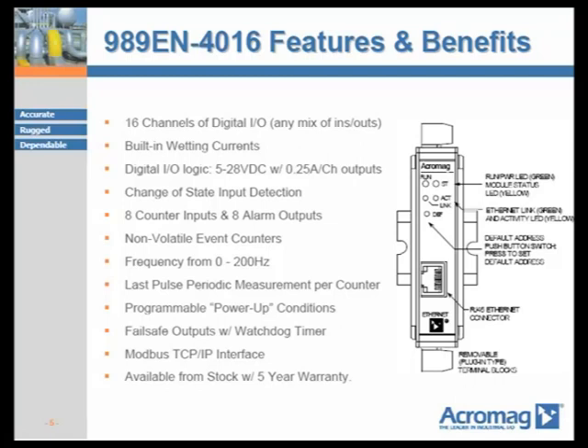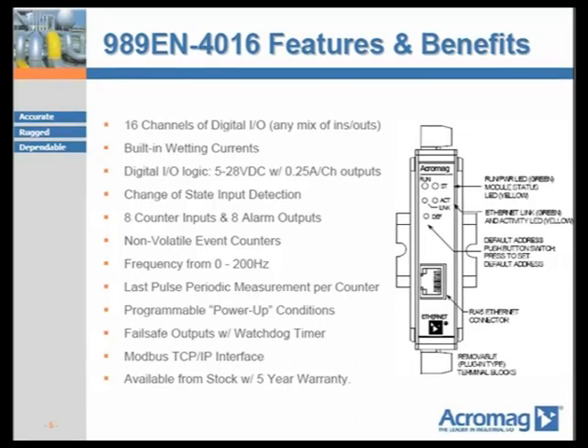Each channel includes built-in wetting current generators, which allow the 989EN to excite dry contacts and extend their usable life by cutting through oxidation that can build up on contacts and cause failure. The 989EN is a completely solid state device with no mechanical moving parts. It can sense or switch dry contacts, proximity switches, and support 5V, 12V, or 24V DC logic systems. Change of state input detection is available for all 16 channels, meaning momentary push buttons can be wired to all channels and the host system can read a special Modbus register to detect changes between polling cycles — ideal for triggering or stopping processes.